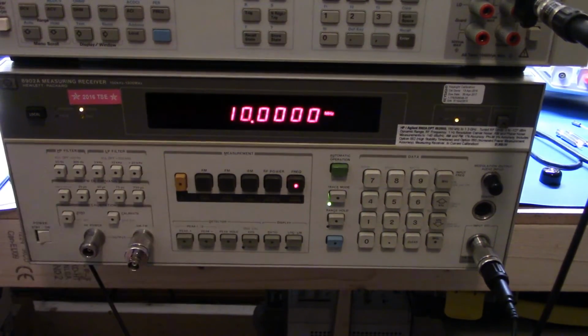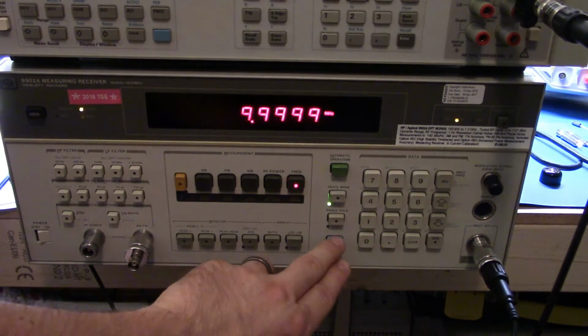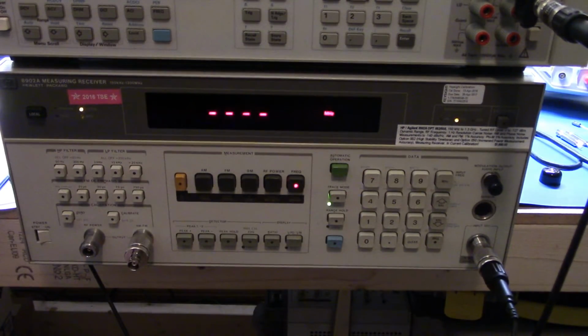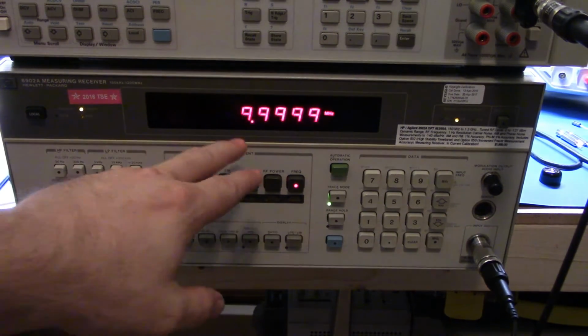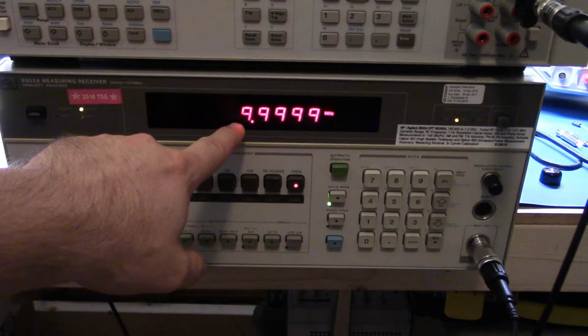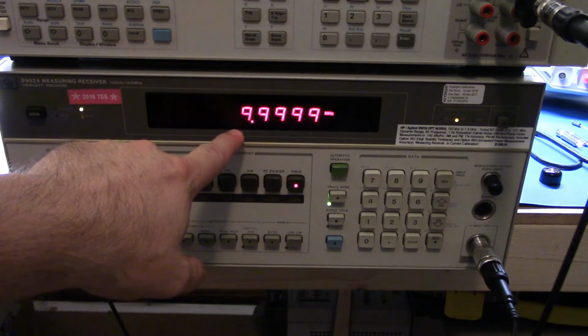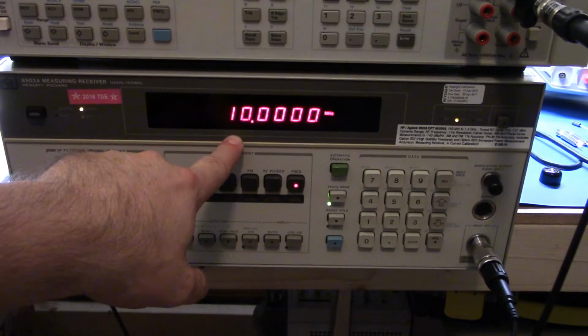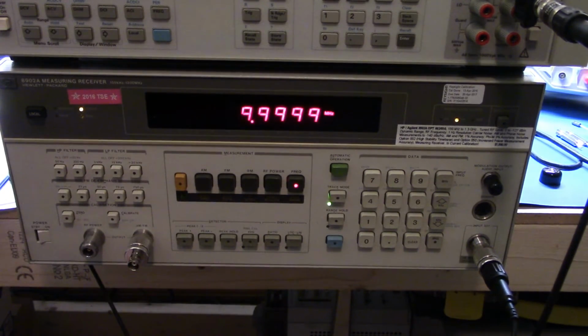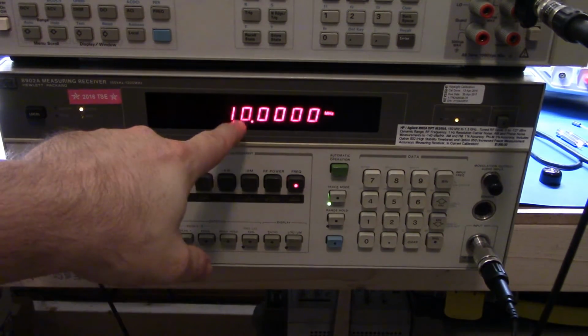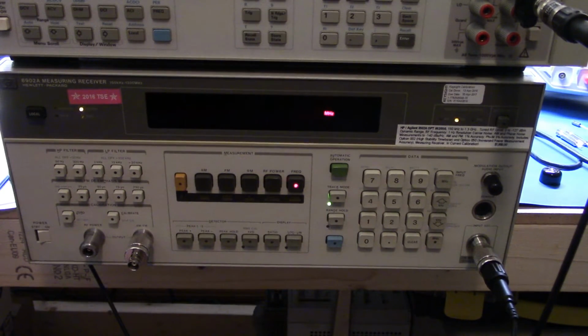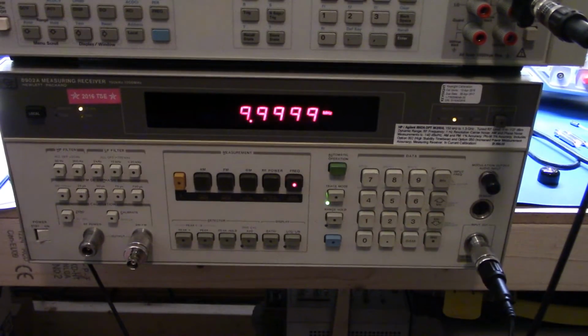Okay, so I just turned the unit on, and we'll just reset it. My signal generator is an 8657B, and it is set for 10 megahertz. You'll notice that the signal is occasionally dropping out, and it's not detecting the signal. You'll see the display will disappear. There we go. Now that's not the only problem with it.